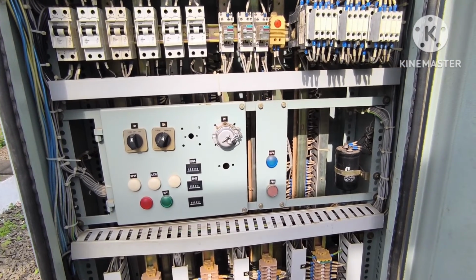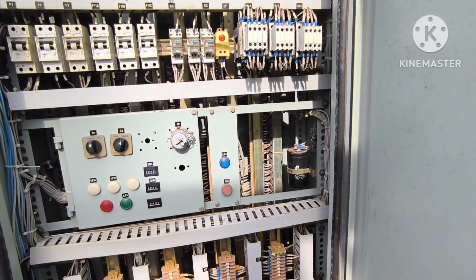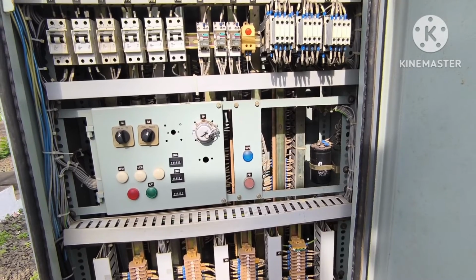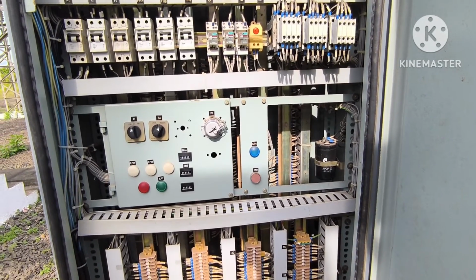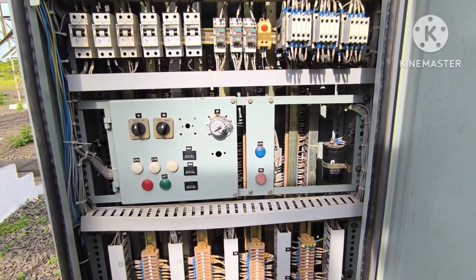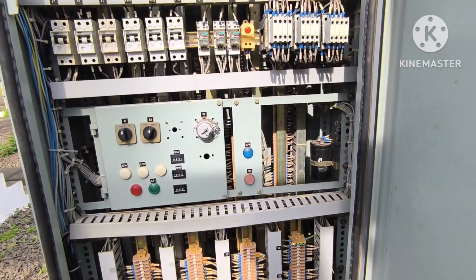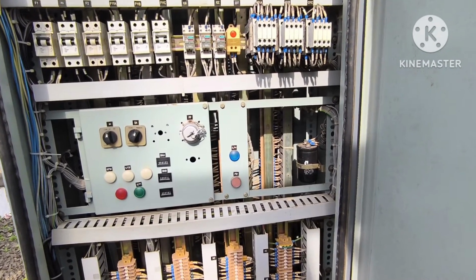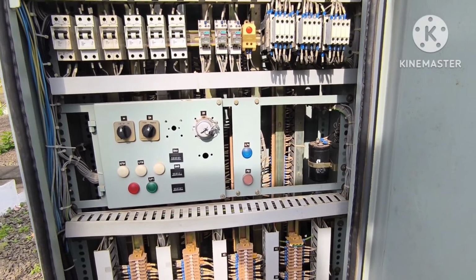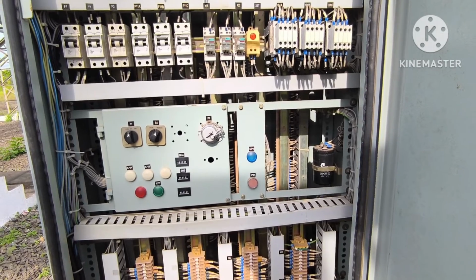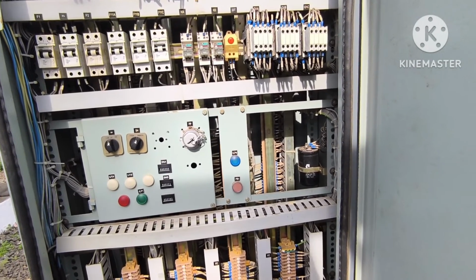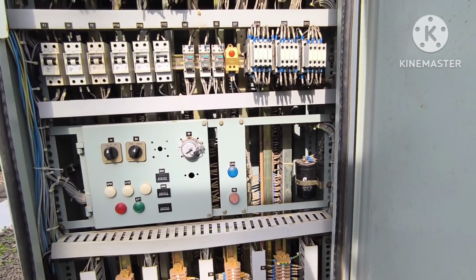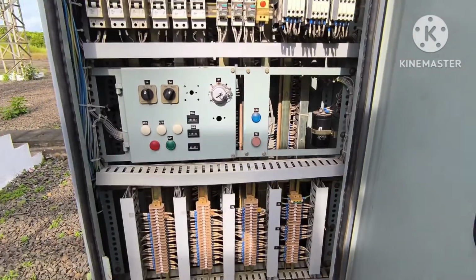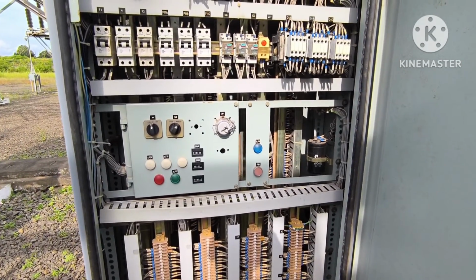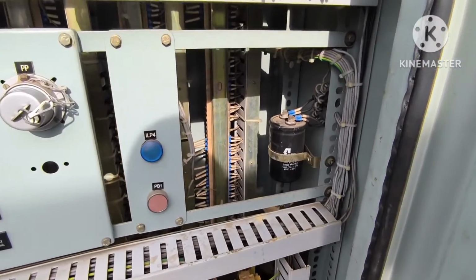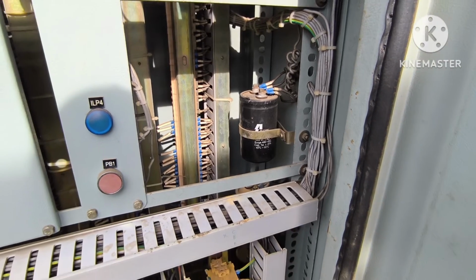Suppose this is a generator bay, and the generator is running, and in the meantime this circuit breaker's DC supply fails. In this scenario, suppose a fault happens in the generator, then the generator protection relay will extend the trip command to this breaker, but it will not trip due to the DC failure. So the breaker is not going to trip in fault conditions. The fault may extend to some other area, LBB may be initiated, and some other breaker will isolate the fault. In the meantime equipment might be damaged. This is the reason this capacitor strip is there. Whenever there is a DC failure, the breaker will trip immediately. This is the utilization of these capacitors. It is 1000 microfarad, 3 capacitors are given.